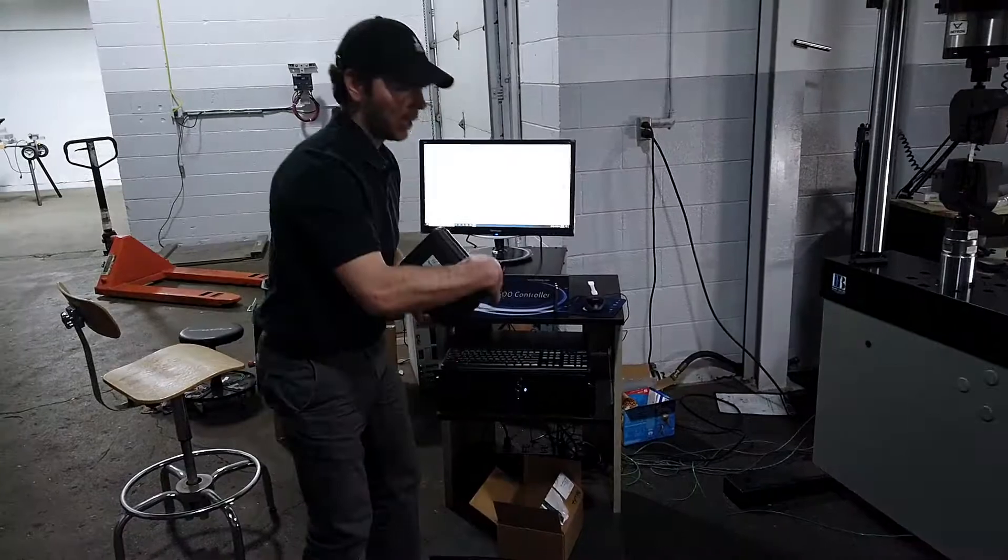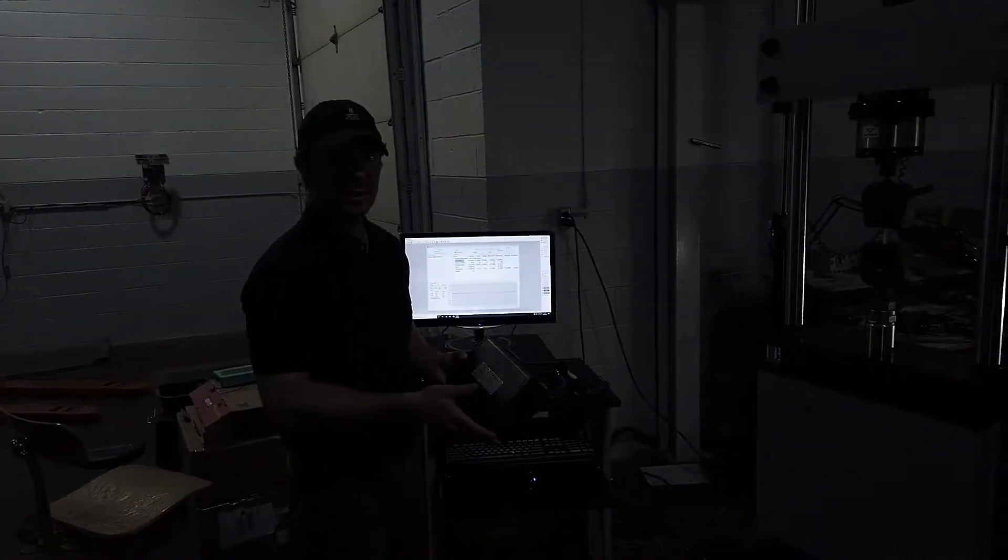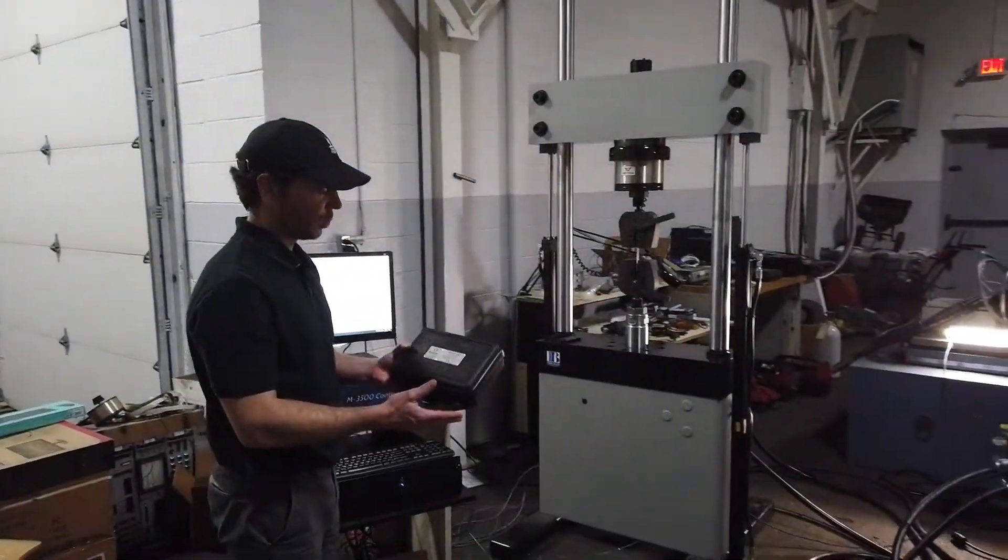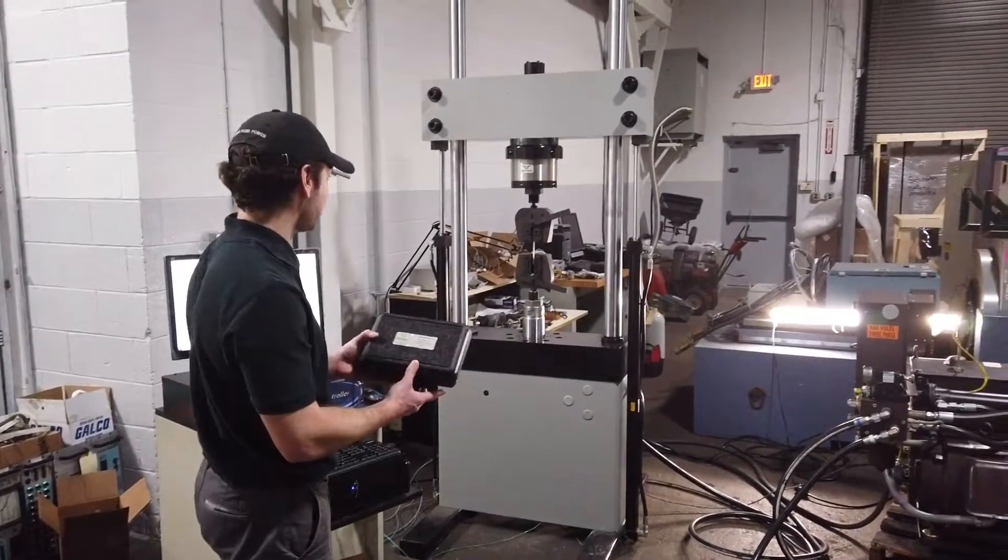So it's a turnkey system. This specimen also went with a new extensometer, so you can get stress versus strain data direct from your specimen, and that can be used both for static tensile compression testing as well as cyclic fatigue testing.